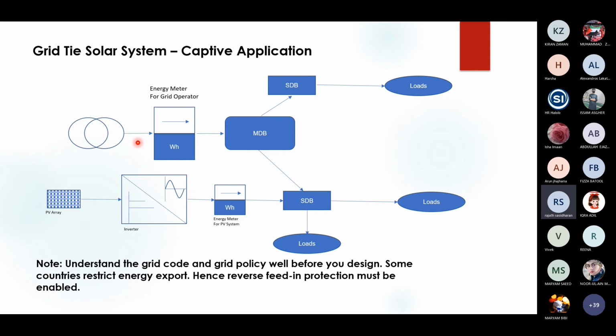In some countries, when we design the systems, we have something called reverse feed protection relays and soft reverse feed protection devices. There would be another CT/VT here with a monitoring box, and that box will tell this inverter to limit its power or go into shutdown. Please take note of this reverse feed in protection. You can read further about such devices. There are relays and power limiters available in the market.